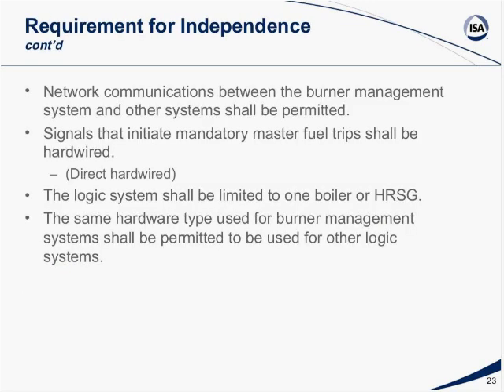So the requirement for independent network communication between the burner system and the control system shall be permitted. In other words, you can have communications between the two systems, but it's necessary to make sure that all your signals go directly to the burner manager or your safety system, and then you can bring that system over to control, but not from the control system to the burner management across the highway. That's not permitted. So initiate mandatory master fuel trip shall be hardwired. Some refer to this as direct wired. In other words, go from a push button or shutdown directly to the shutdown relays.